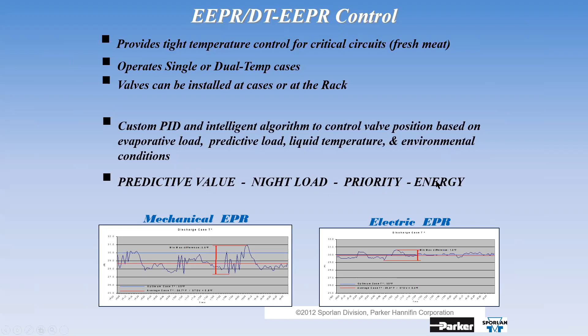We were able to set it up for either single or dual temp. The biggest thing I want to talk about is that we were able to put an intelligent algorithm into that which controlled the valve position based on evaporative load, sensible load, predictive load, liquid temperature, and the environmental conditions in the store. And we were also able to tell one of the EPRs to be priority, and the other ones were energy savings. Okay? Any questions about that at all?